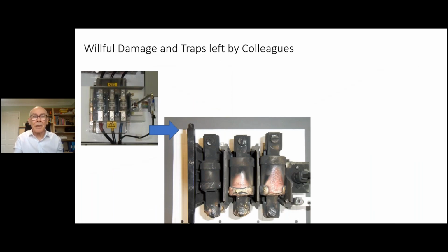This is another case I was asked to investigate after an injury from an electrical flashover. I was asked to investigate an incident that caused injury to a facilities technician fault-finding on a control panel. The picture on the left is a healthy main switch, and on the right is the damaged unit involved in the flashover. The arc flash was caused by persistent low-level arcing across the contacts while on load, so the contacts weren't quite making, and eventually that escalated into a full arc flash. Remember the model I showed earlier, where you've got discharge in air. At some stage it becomes a short circuit, and that's what happened here.